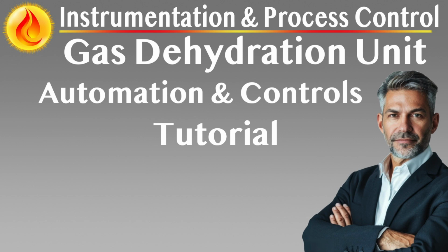Internal level and separation control, rich glycol and condensate interface management. Chimney tray level monitoring. Liquid level between glycol and hydrocarbon condensate in the chimney tray, if skimming is used, is monitored to prevent carryover to the regenerator. Level interface transmitters, LIT, or guided wave radar devices detect high levels of hydrocarbon intrusion.